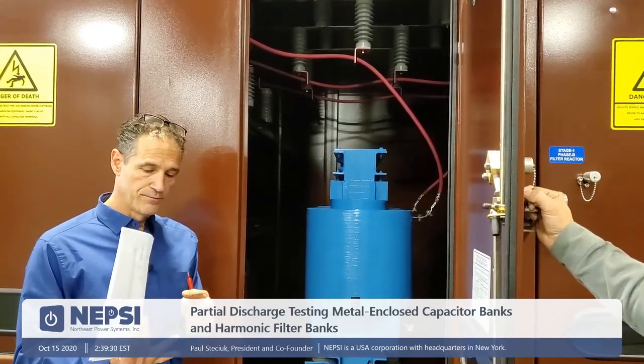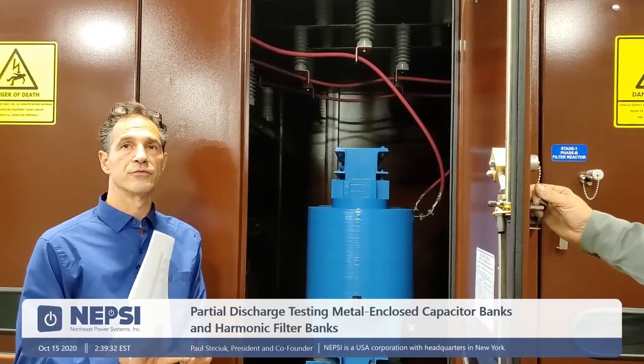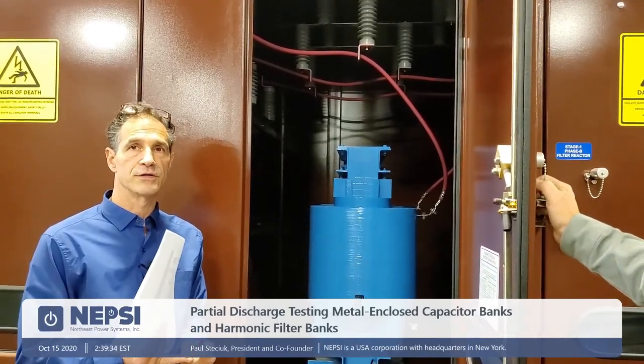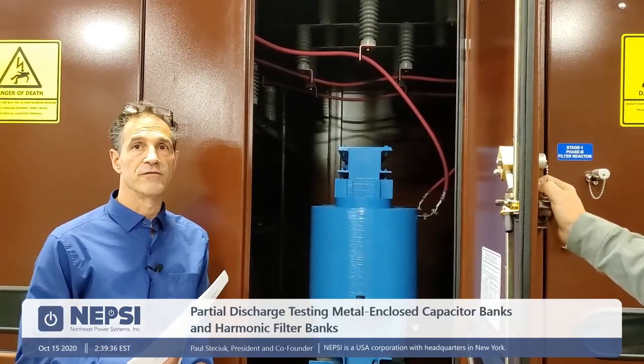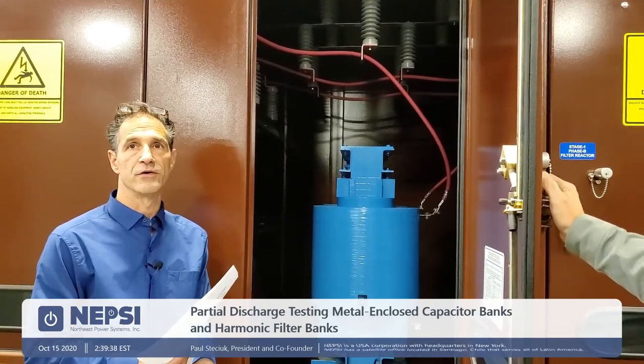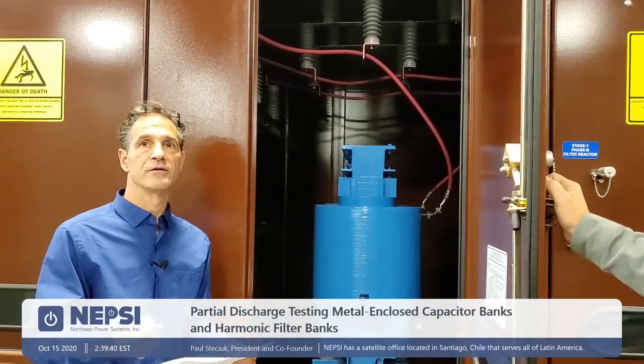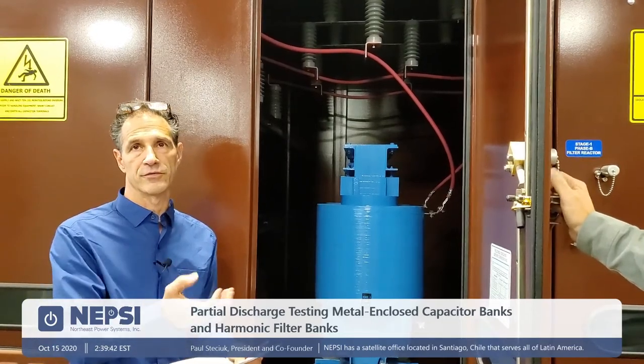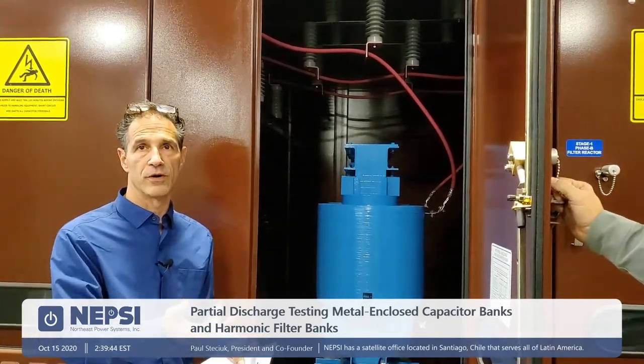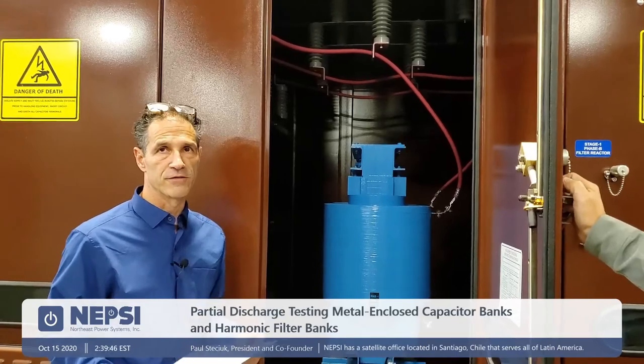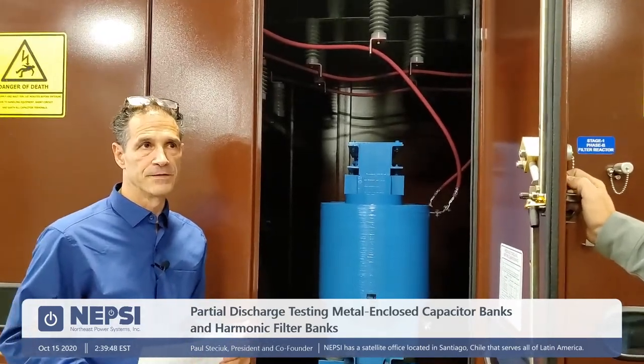If we have a real bushing that has both a high voltage and a ground shield in it, we might find that one of those bushings could fail also because of a defect from the component supplier. The component came to us and, say it has air bubbles inside, it could potentially fail at that point too.